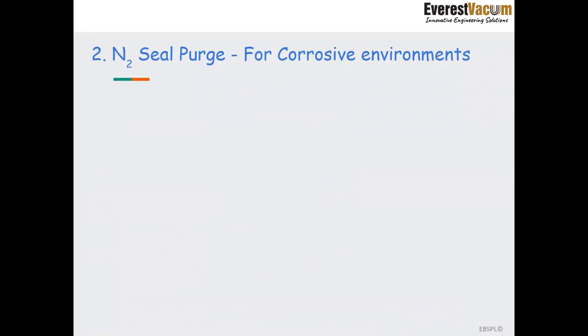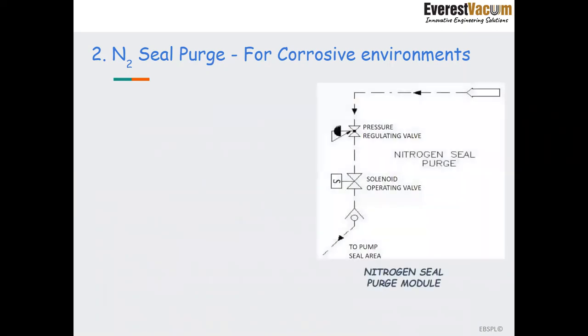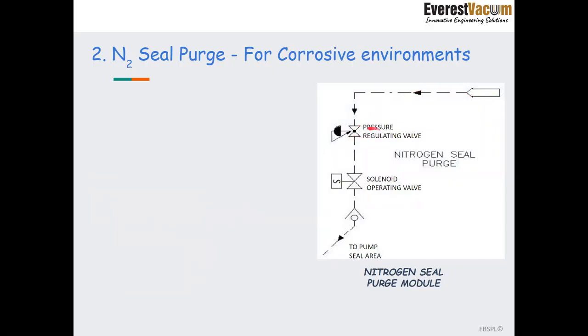Another module very effective for corrosive environments is the N2 seal purge. The module looks like this. This is the inlet for the nitrogen gas. Then there is a pressure regulating valve to regulate the pressure, because there is a certain operating pressure that is required. And then there is again an actuated solenoid valve, and this goes to the pump. There is an NRV in this line to provide unidirectional flow. There should be no backflow, so that is why the non-return valve has been installed over here.